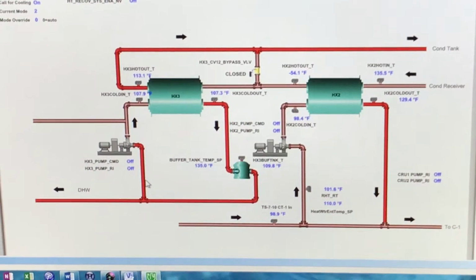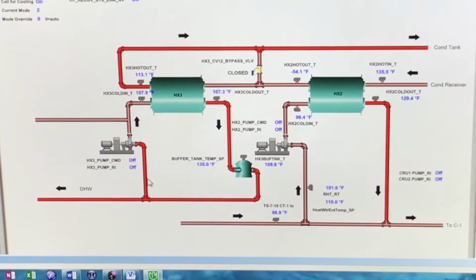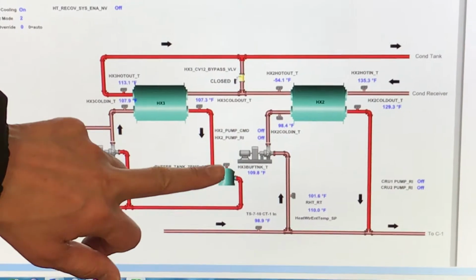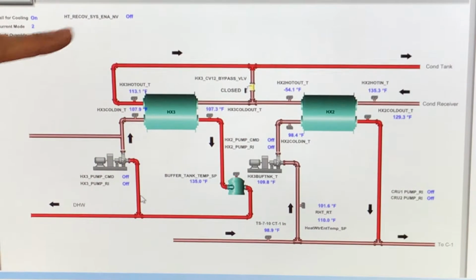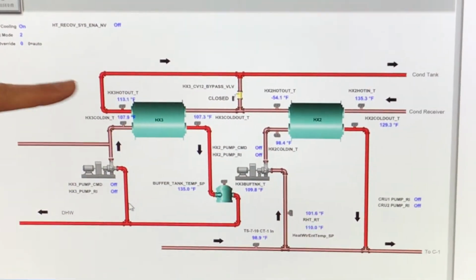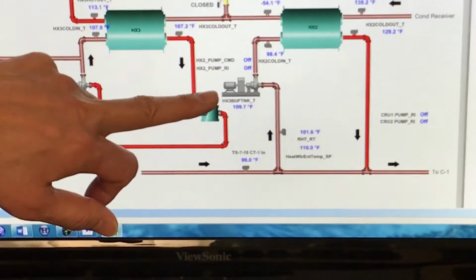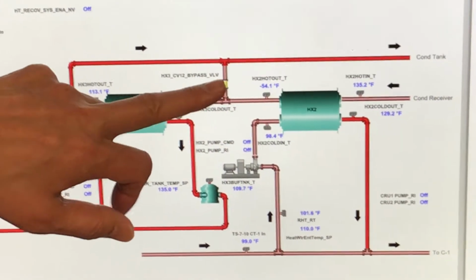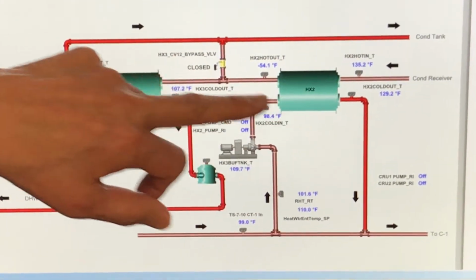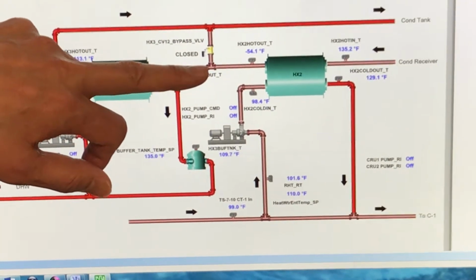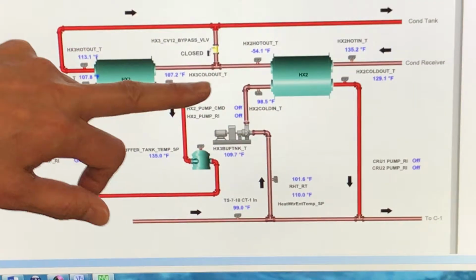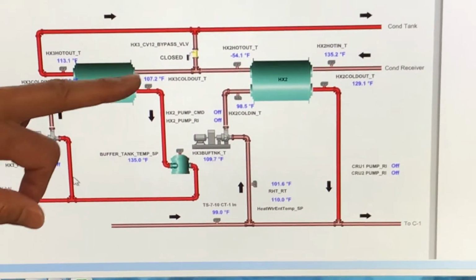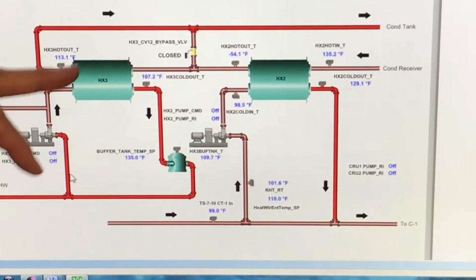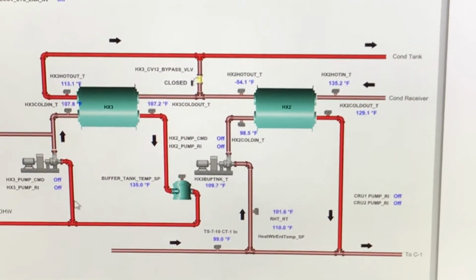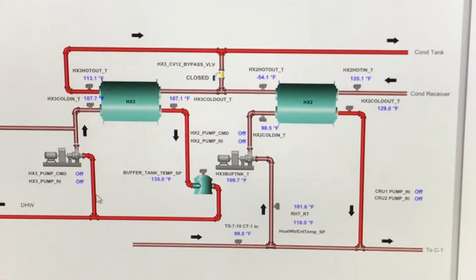Yeah, this is a valve, the hot condensate valve, that I'm talking about. Normally the steam condensate goes through here and through there, all the time, basically. When that temperature gets too high, if you open this valve up, then some water, not all, hopefully most of it, will go through here instead of through there, and then there will be no heat transfer. And then this temperature hopefully will drop down, and that's what we are trying to do.